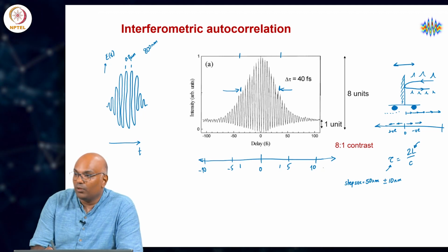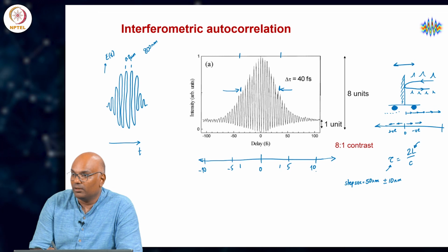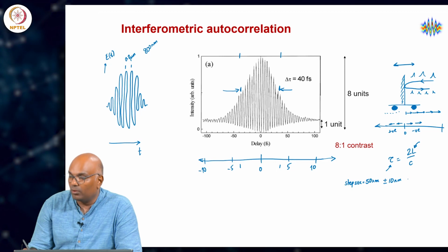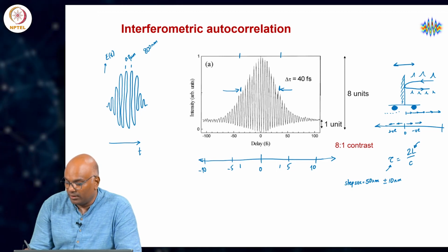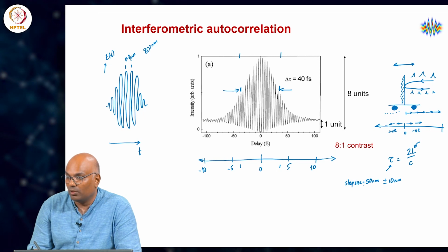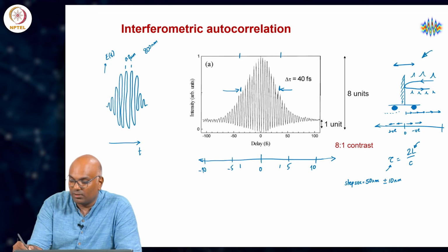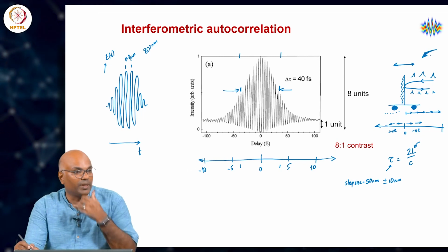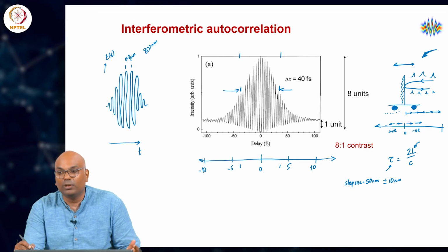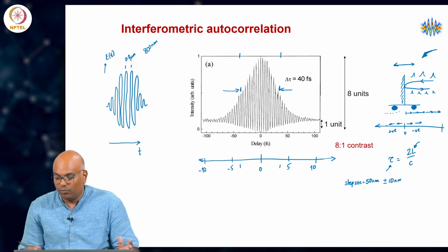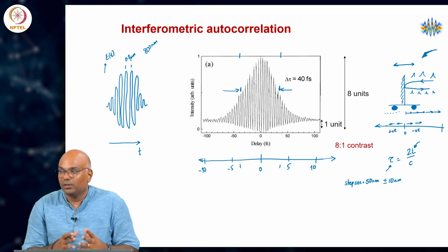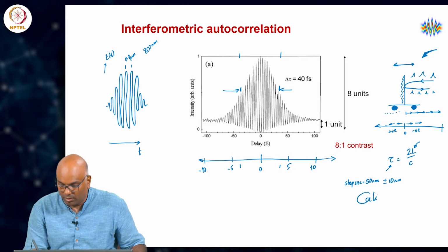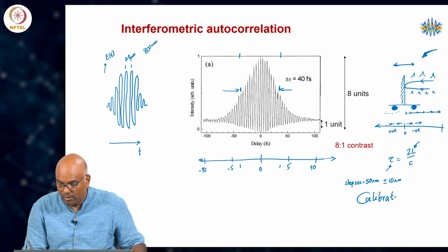So, the integrity of the horizontal scale, distance scale, which is in reality what we have in a laboratory, is entirely incumbent on the quality and the integrity of the stepping process of this micro or nano positioning stage, and all these systems are engineered, made, and they could have their own error and whatsoever. So, what do we need in order to fix this arbitrariness in this metrology problem? What we need to do is a calibration.